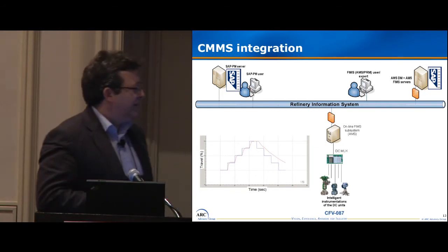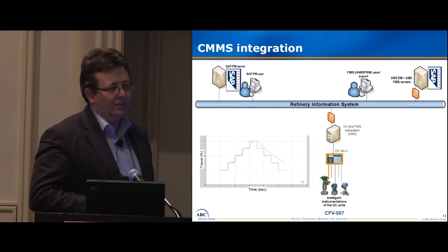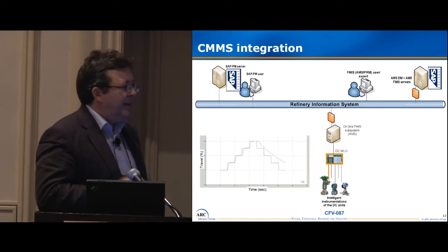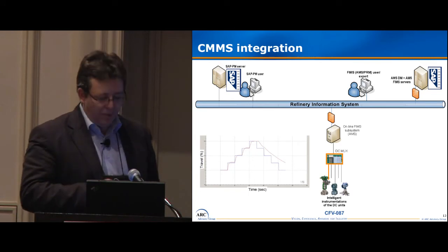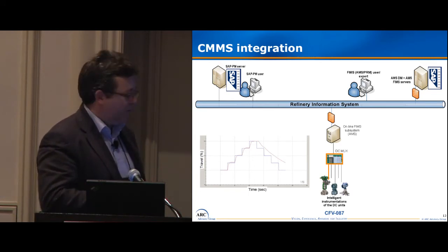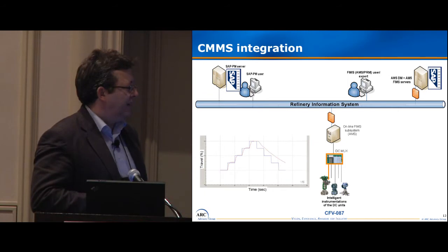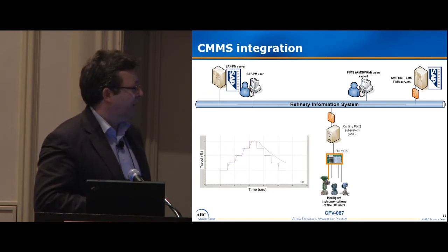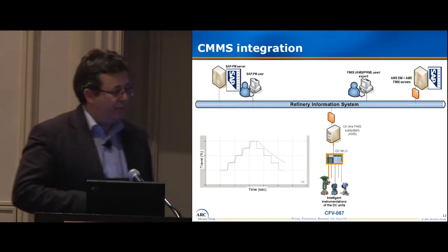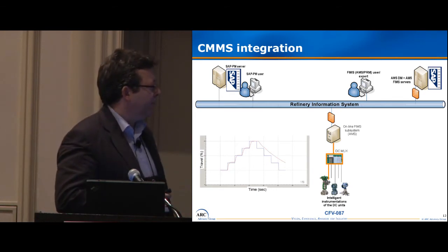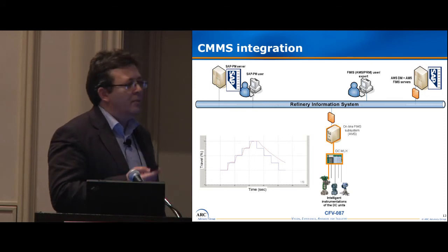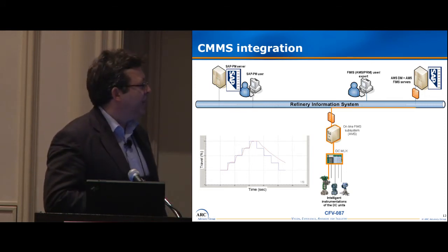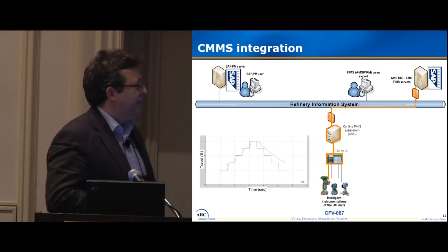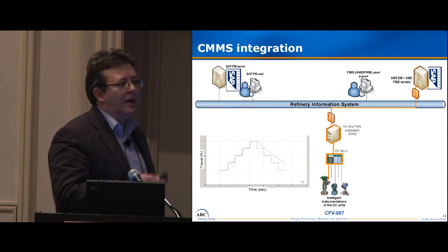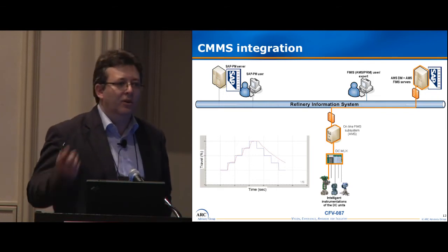If we have an intelligent positioner on the control valves, it immediately sends preventive information, a preventive signal, to the DCS, and the signal goes to the field instrumentation management system, integrated into a central AMS or PRM system. We have dedicated staff to analyze whether it is a critical event or not.